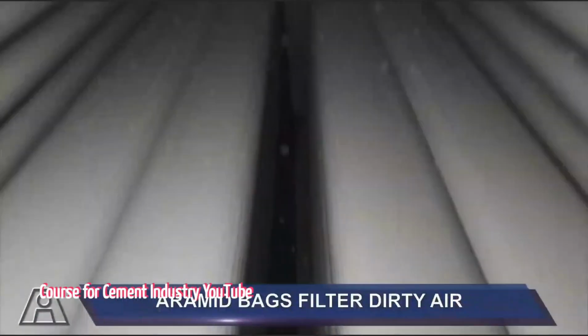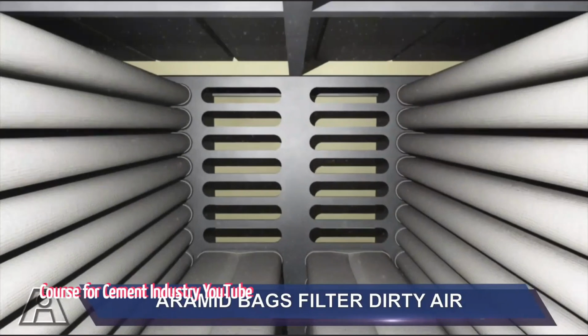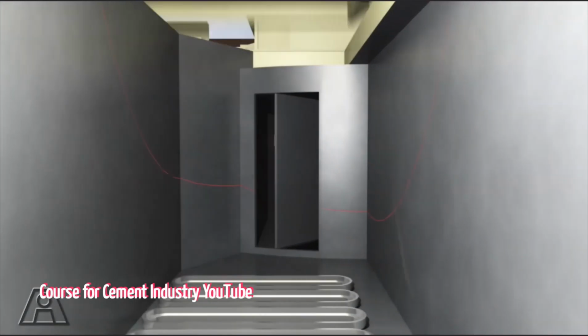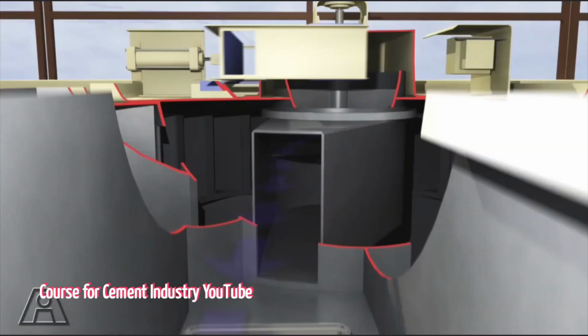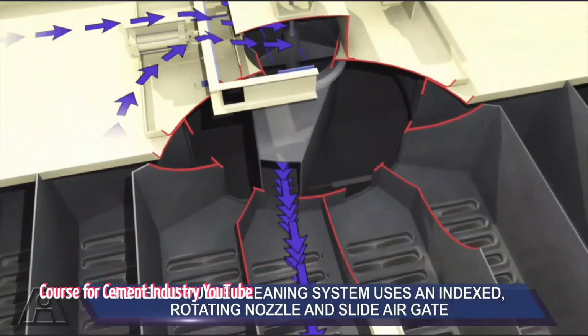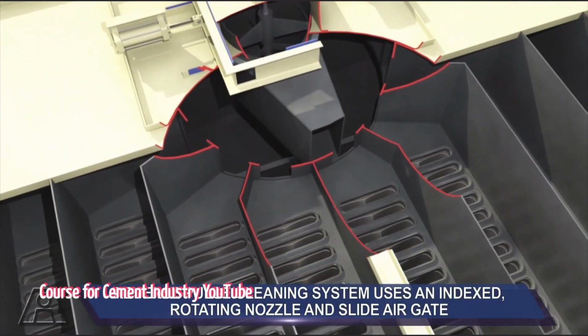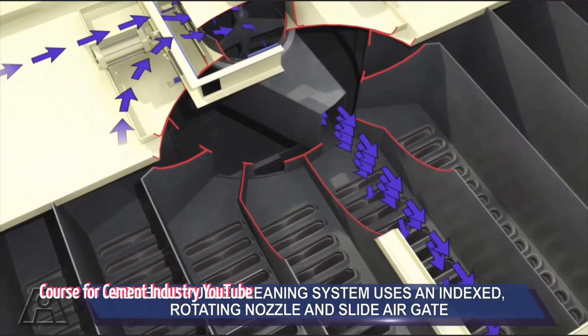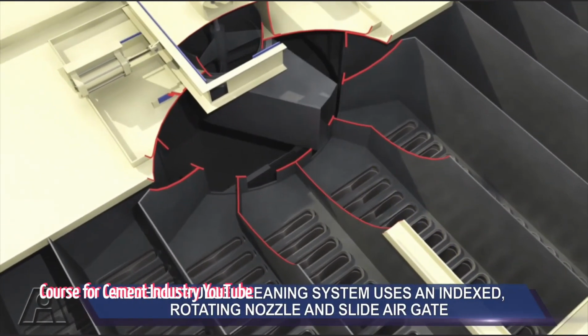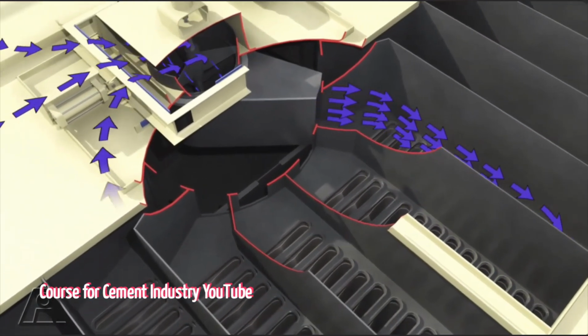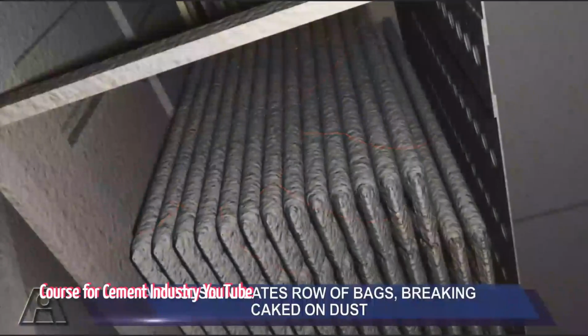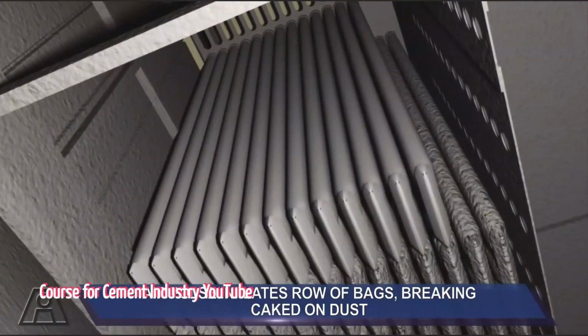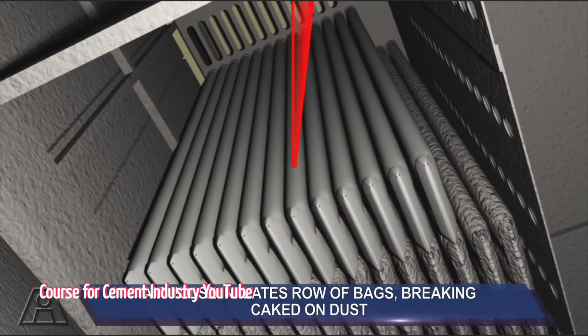Pulse jet. Okay. Basically, the system uses blasts of high-pressure compressed air. This air is stored in tanks and then directed down into the filter bags, one row or section at a time. Wait, you blast high-pressure air into the filter bag, the thing that's supposed to be filtering? Yep, it's a very short, sharp pulse, though. We're talking milliseconds. Okay, a quick burst, but still, high pressure onto fabric. Doesn't that damage the bags over time? Seems like there'd be a maintenance trade-off.